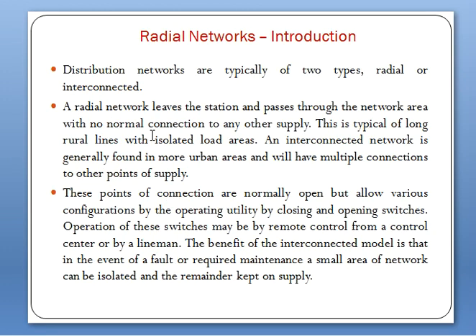The distribution networks are typically of two types, radial or interconnected. In the radial network, there is no normal connection. A radial network leaves the station and passes through the network area with no normal connection to any other supply. This is typical of long rural lines with isolated load areas.